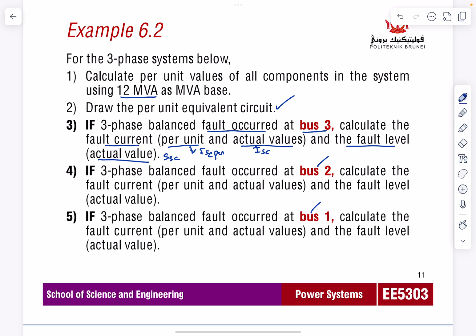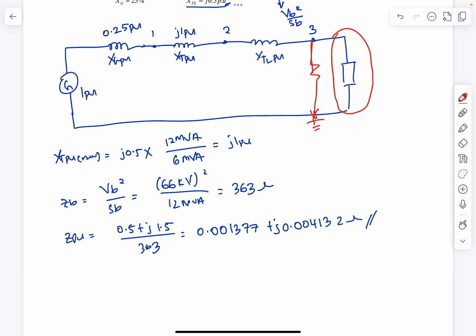For question number 3, now that you've converted all the values into per unit, the next step is to calculate the fault current in per unit and actual values. This means: if a fault occurs at bus number 3, what happens to the load? The load will be ignored because the current will flow toward the fault instead, giving us the short circuit current ISC.